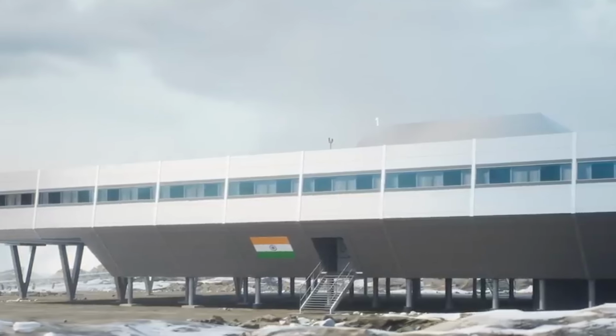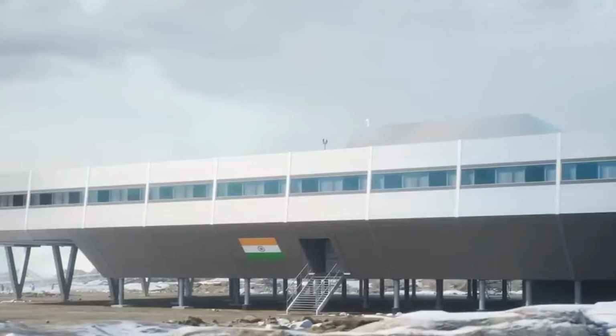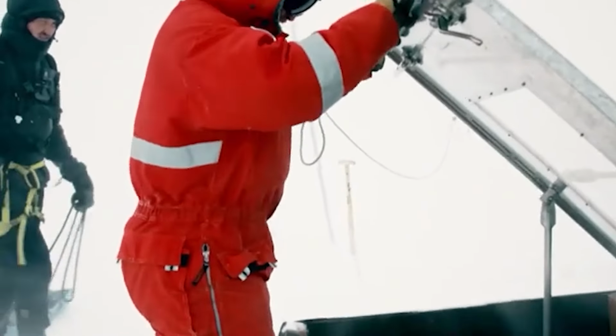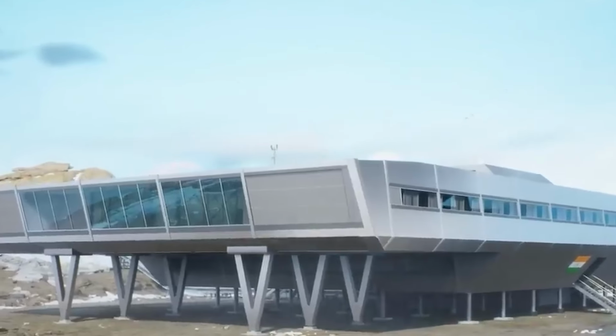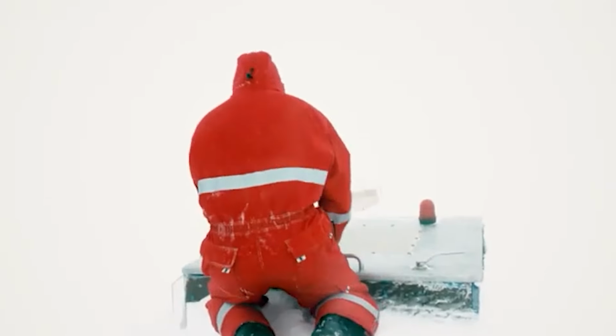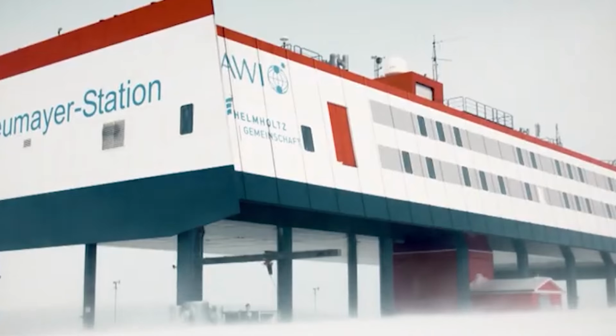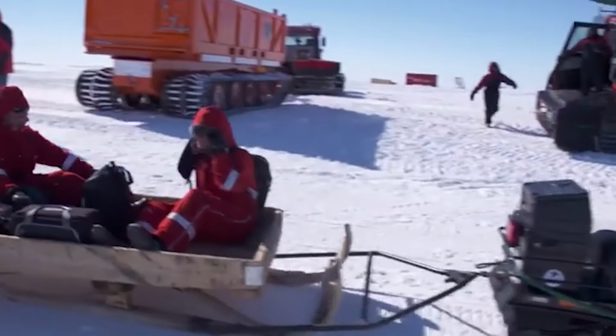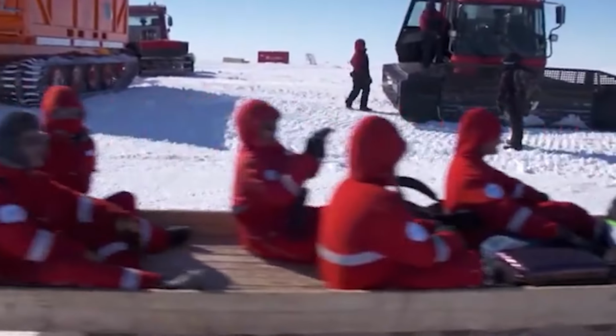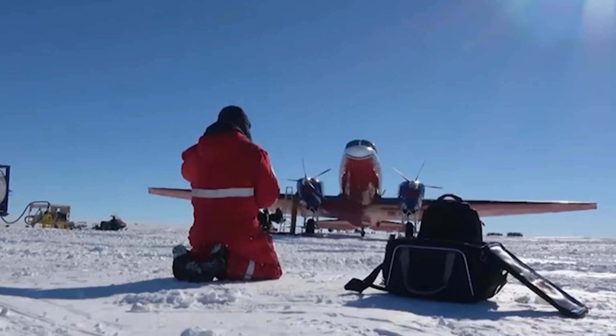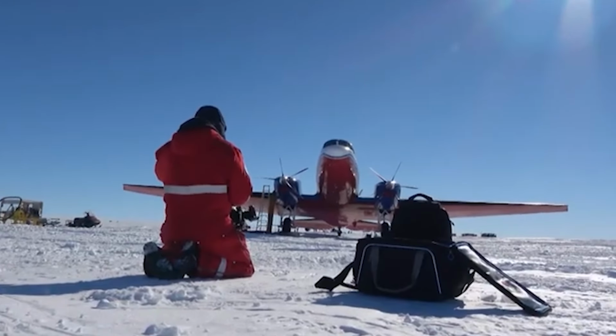Diesel fuel fails even earlier. At around -15 Celsius, cold, but nowhere near Antarctic extremes, diesel reaches what's called its cloud point. Wax crystals begin forming in the fuel. The liquid turns cloudy. Drop the temperature further, and you hit the pour point. The fuel gels into a thick sludge that clogs every fuel line, every filter, every injector. The engine starves. It cannot run.